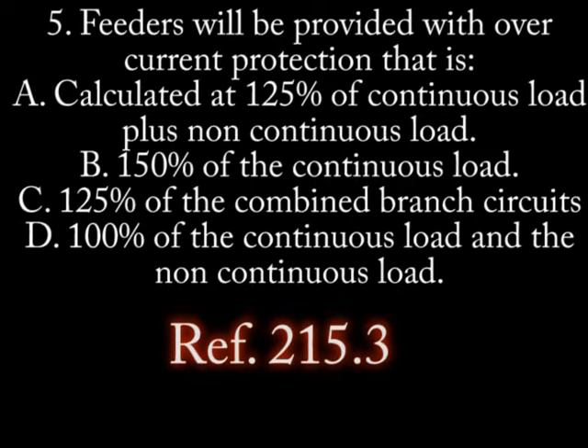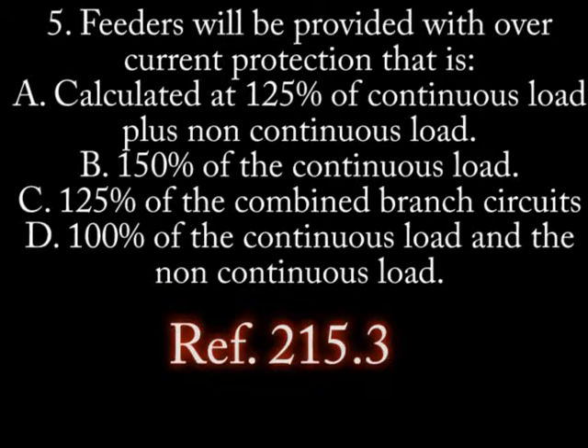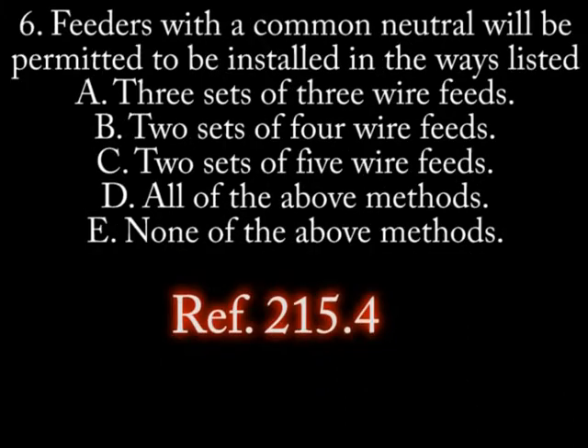Number 5: Feeders shall be provided with overcurrent protection that is: A. Calculated at 125% of the continuous load plus the non-continuous load. B. 150% of the continuous load. C. 125% of the combined branch circuits. D. 100% of the continuous load and the non-continuous load.